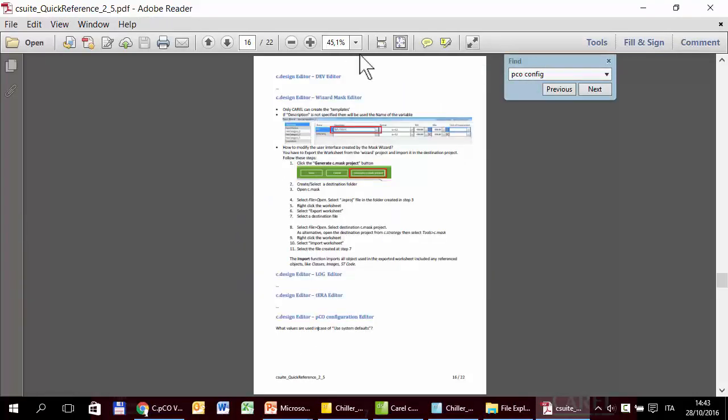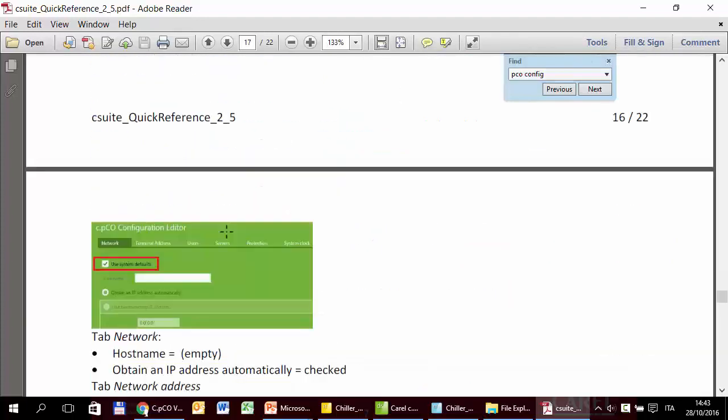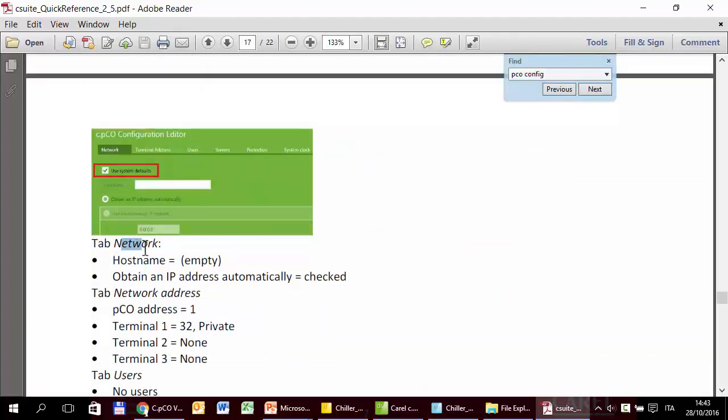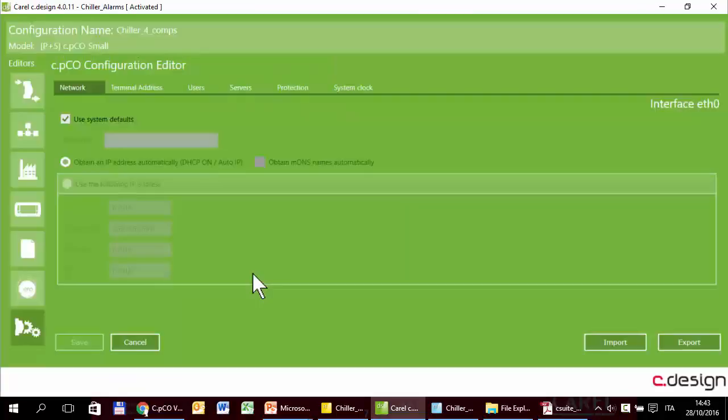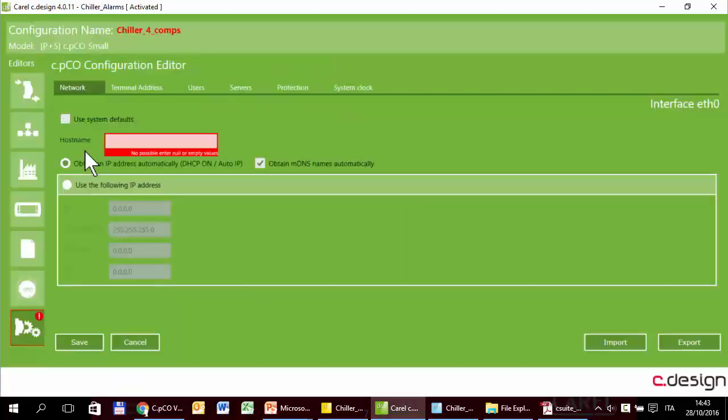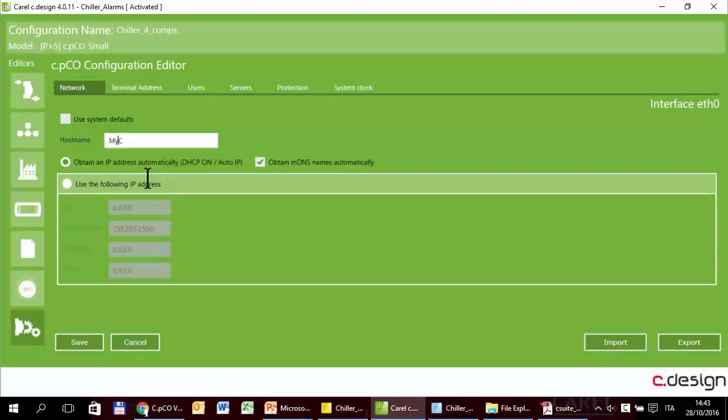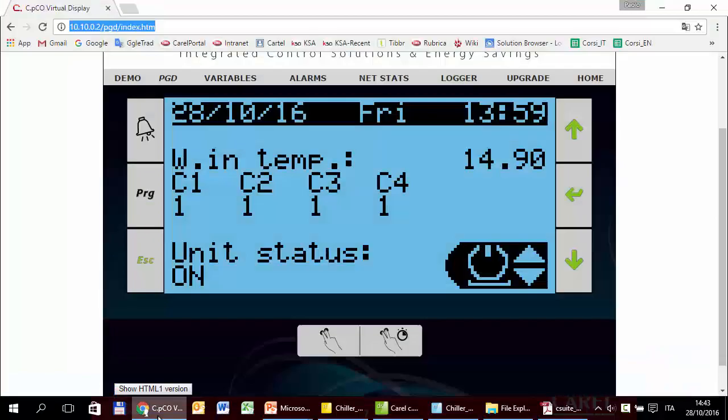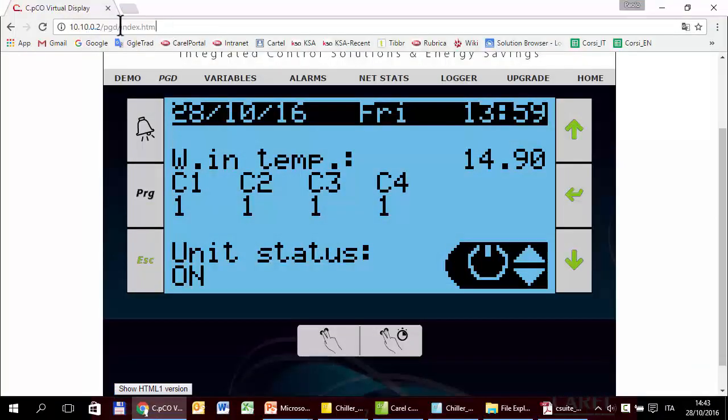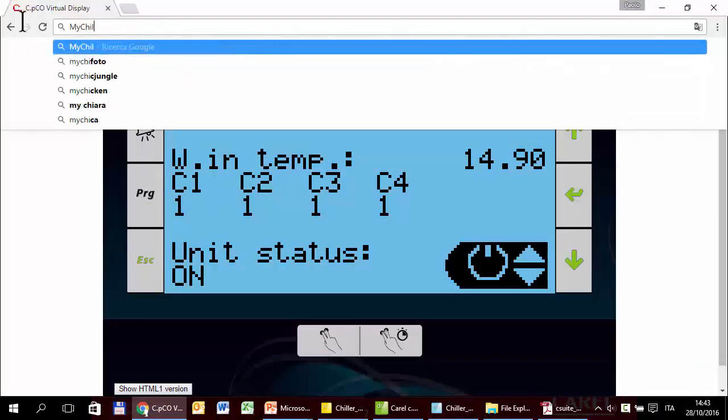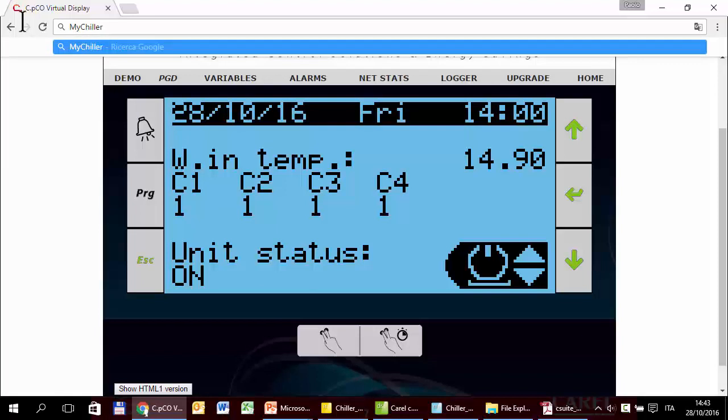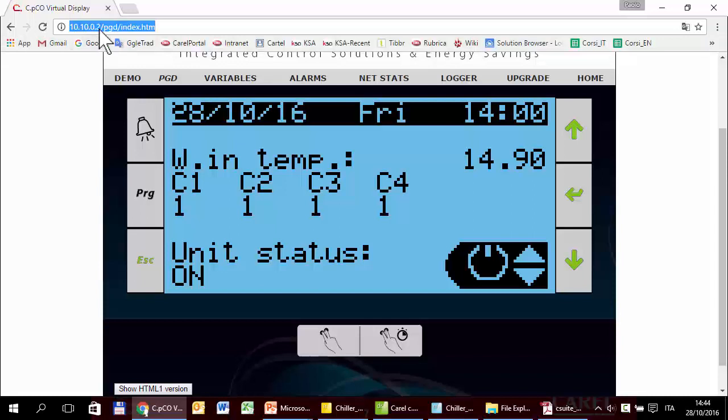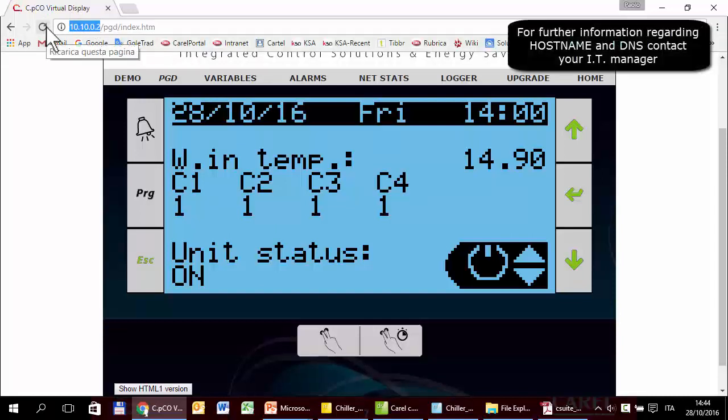For the network, the host name is empty, the obtained IP address is set automatically, that is in DHCP. The host name, like myChiller, allows to define the host name of this controller. This lets you write here, rather than the IP of the controller, myChiller. But to do this, the local network where this PC is connected must be connected to a DNS server that is able to translate this host name with the real IP address of the controller. For more information, you can contact the IT manager of your company.